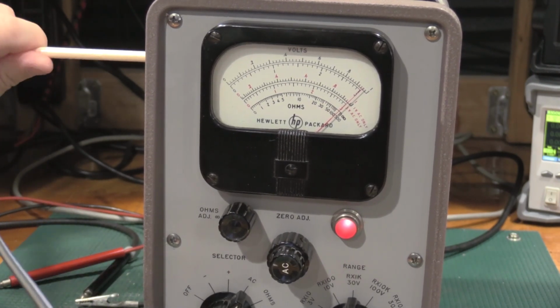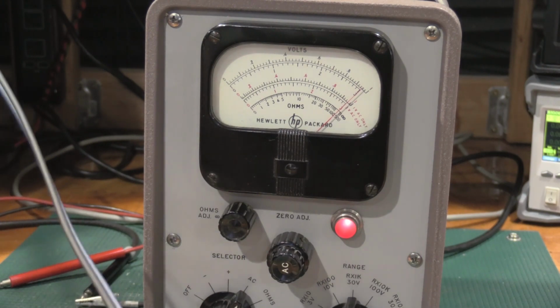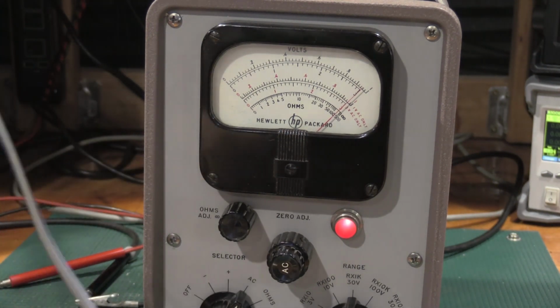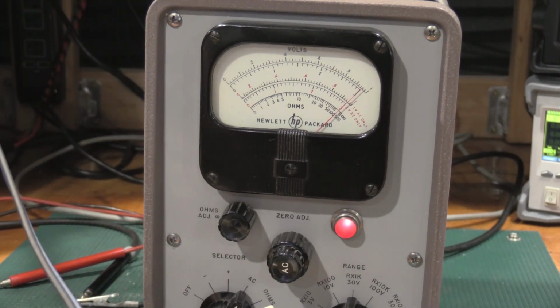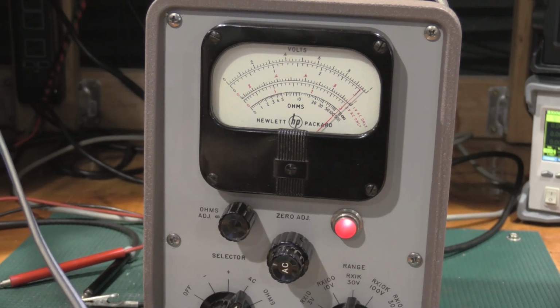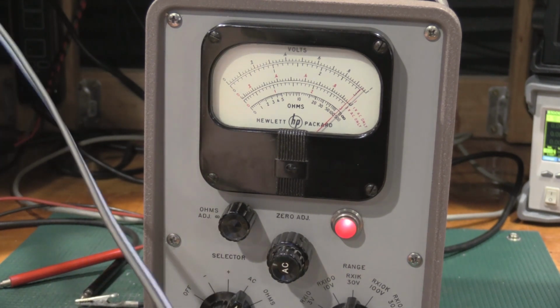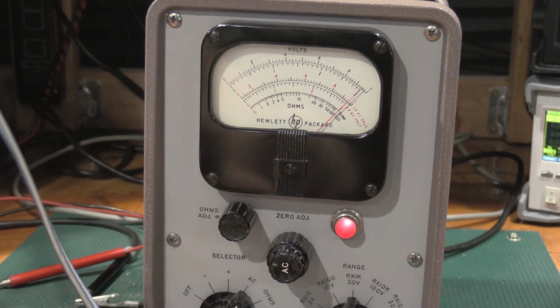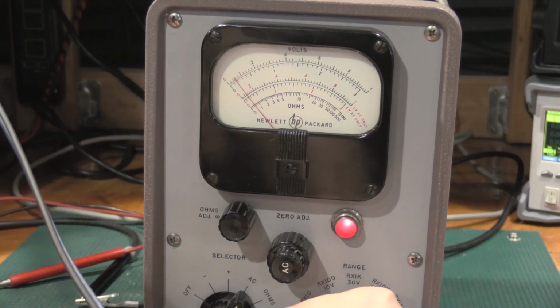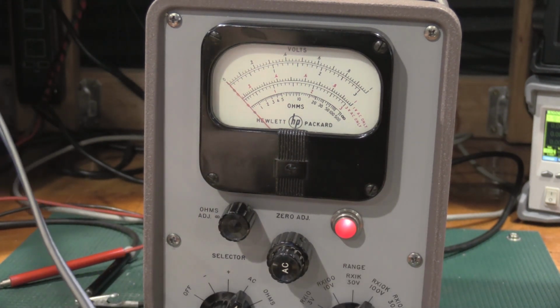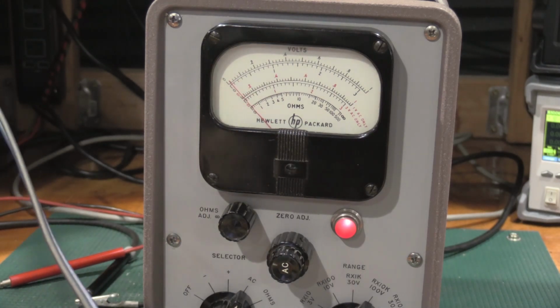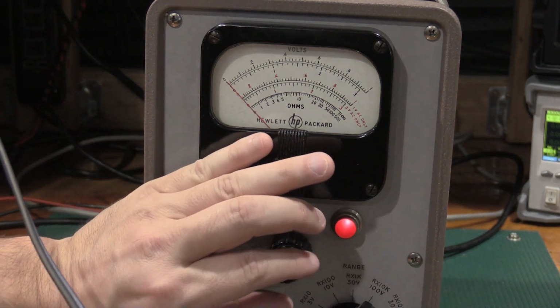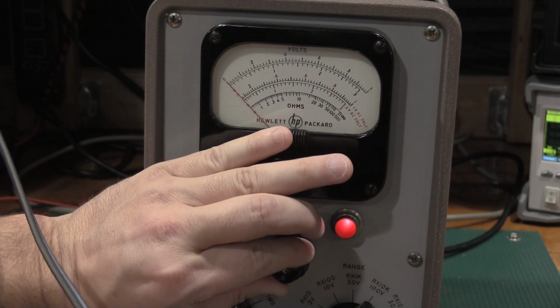A lot of that meter bouncing around was because the controls hadn't been exercised in a while. I don't want to bang around the needle if I don't have to. So having exercised the controls, if they're still scratchy, I'll get a little cleaner and hit it in there and do that. But next up is the 1 volt range, or the 100 volt range. So we'll do this and see how the meter's off just a touch.